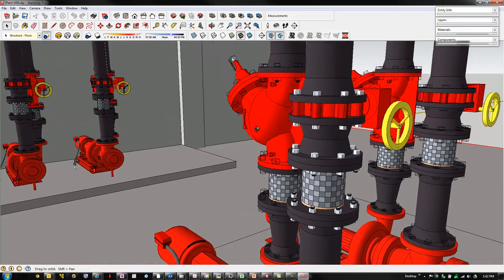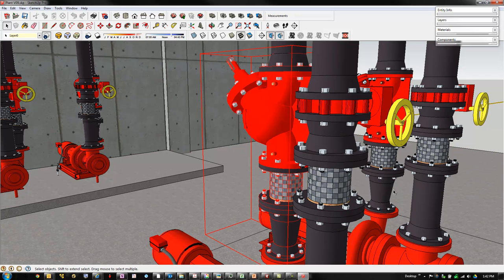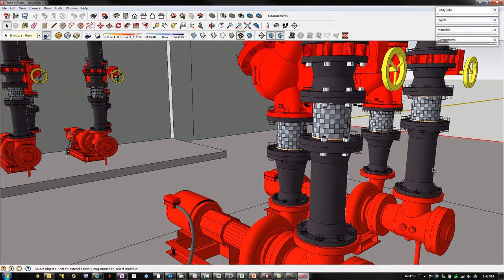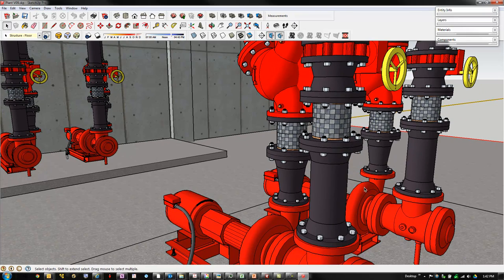Another trick to figuring out which way the water's going when you're out in a plant is to just sort of ask yourself, well, how does a pump work? These are centrifugal pumps. And centrifugal pumps are just a disc with some vanes on it that fling the water, and so the water has to flow into the center of the disc and gets flung out to the sides. I kind of think about it like the merry-go-round I take the grandkids to. You spin them and they get flung out to the side, and they giggle and stuff like that. And the water probably doesn't giggle, but maybe gurgles.